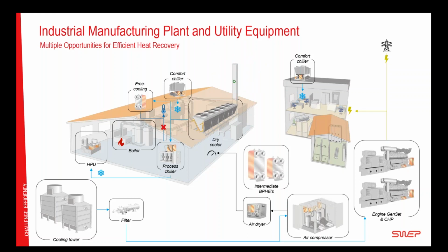So now we have intermediate brazed plate heat exchangers to collect and redistribute the heat for energy recovery. So where can we get heat from? Well, we can get it from the normal chillers. If we're using the superheaters, we can get temperatures at pretty high values, 140 to 180 degrees, which is of high value. From the air compressor and the genset, or combined heat and power system at this point, we can get also energy at high temperatures of high value, which we will again look into more in detail later on. So now we see where we can collect energy.